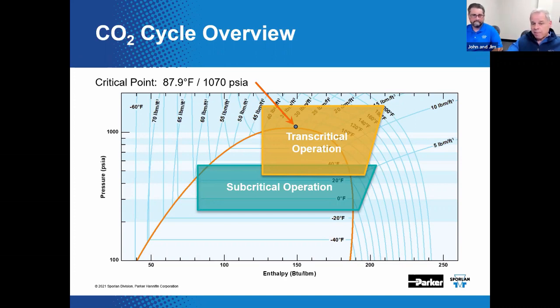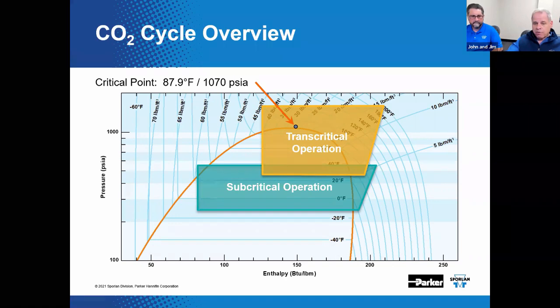Okay, so above this temperature, the refrigerant will not condense when heat is removed. Correct. That means in transcritical mode, the system is operating as a normal DX system using CO2 throughout the system, but above the critical point. And it means in subcritical mode, the system design will typically utilize a direct expansion HFC rack to cool the CO2 on the low side of the system. It can. The CO2 will either be pumped or compressed. We'll discuss that in further detail.